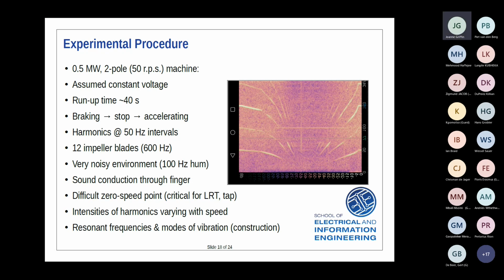This is a 2-pole machine, running at 50 revolutions per second, so we expect harmonics at 50 hertz intervals. Just out of interest, this machine had 12 impeller blades, so walking into the factory I was expecting to measure a 600 hertz harmonic - 12 times 50 giving 600 hertz.